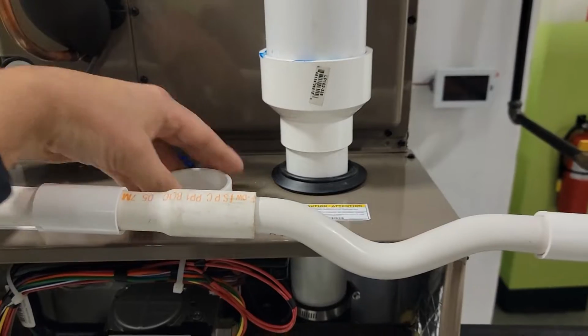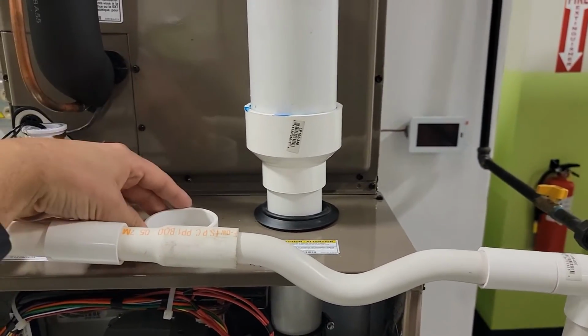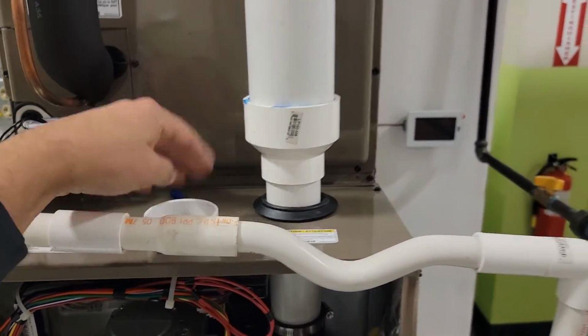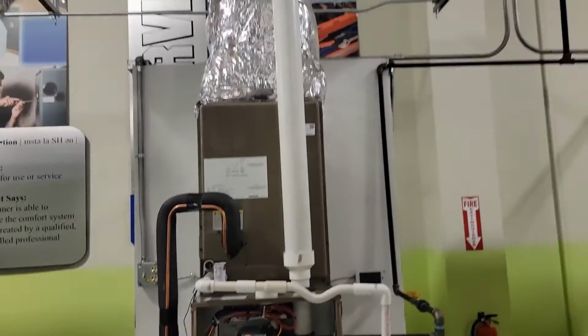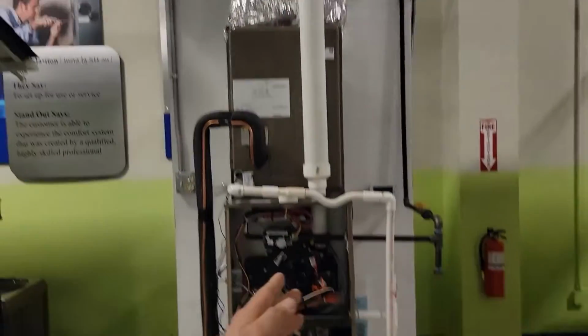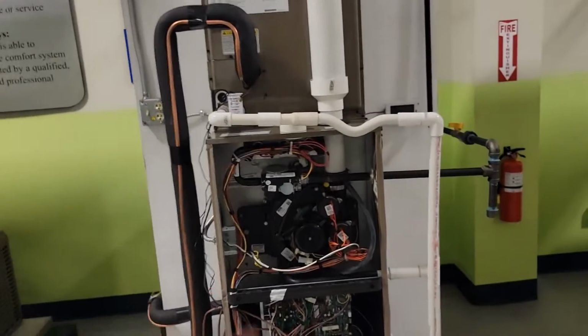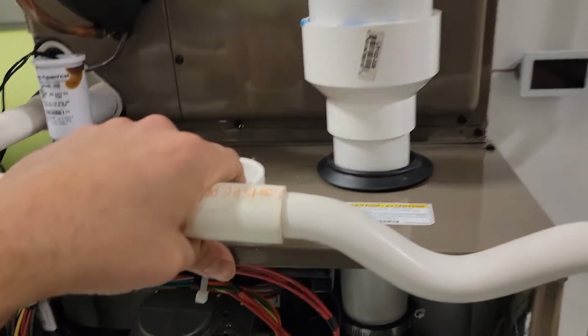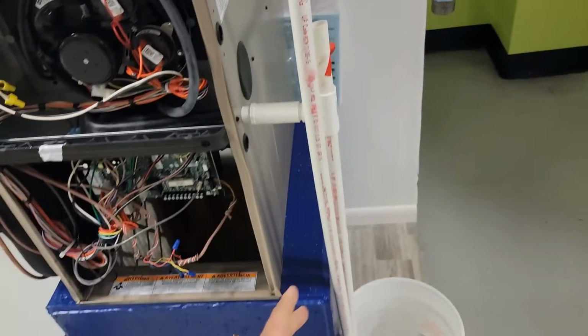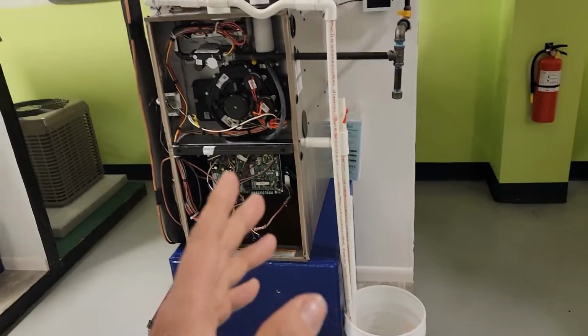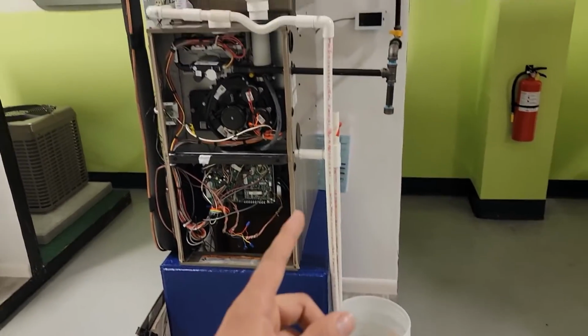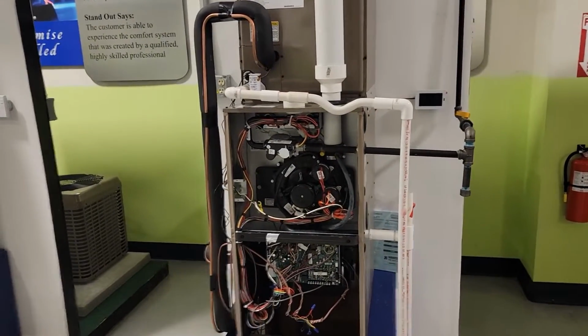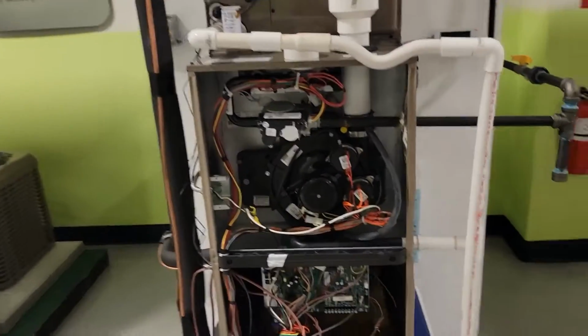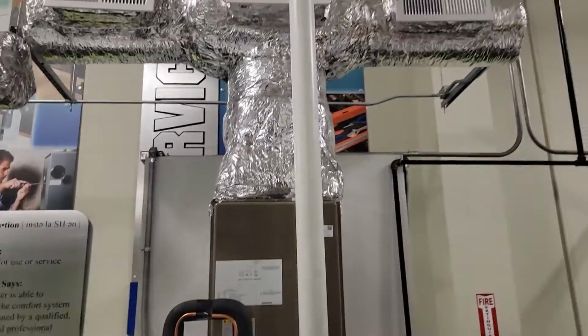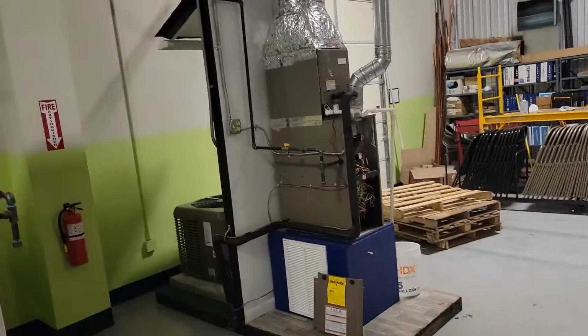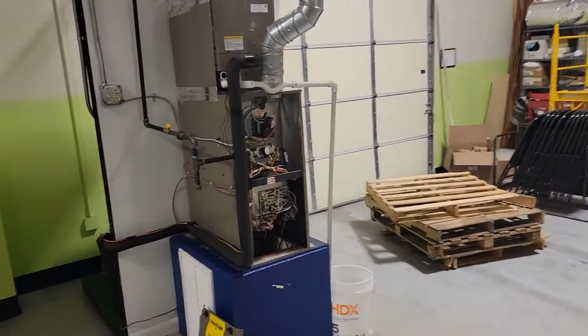Or if you need dedicated fresh air, you run a fresh air pipe from outside of the building or the home so that you can pull in fresh air. Another good thing about the 90% furnace is the vent pipe can be run vertical or horizontal, so you have a lot more options for your venting. Remember, of course, though, it is condensing, and if you are in a climate where it gets way below freezing, then you may have a frozen drain, and then of course that's going to make your furnace inoperable. It is not going to work. So love 90% furnaces though. They are awesome when you have the right application.